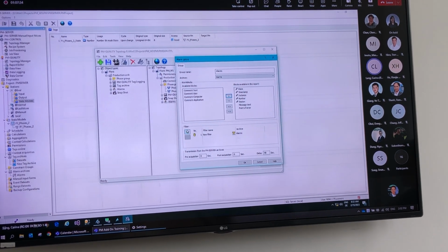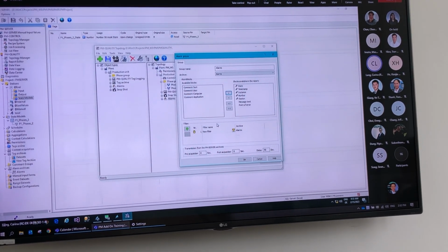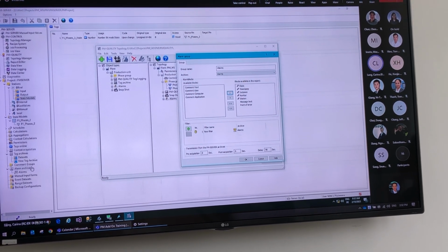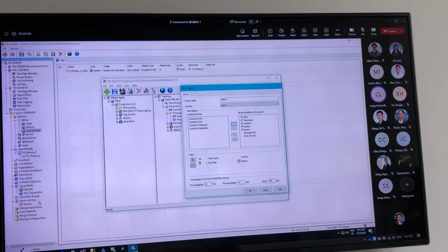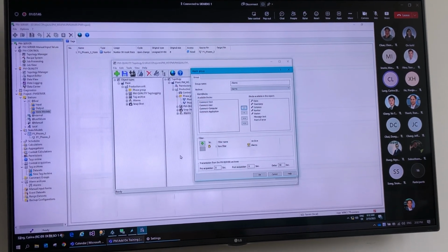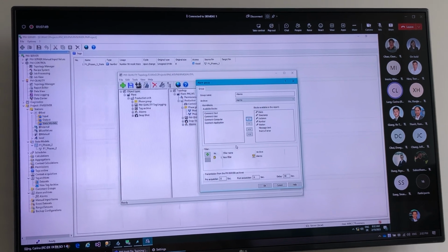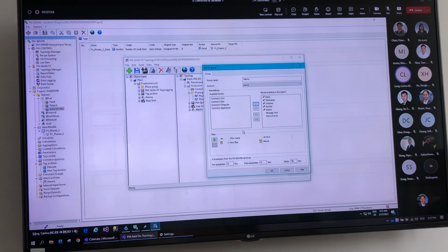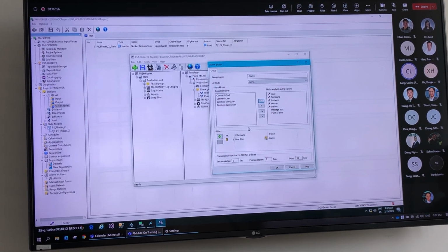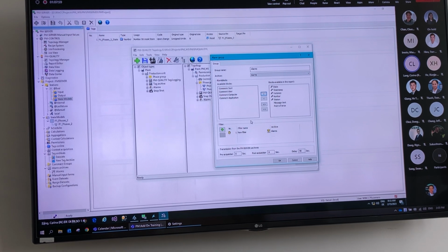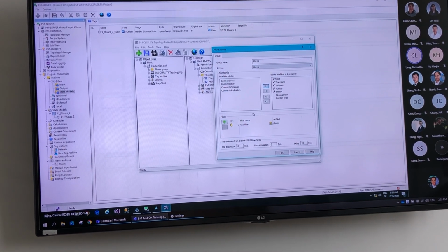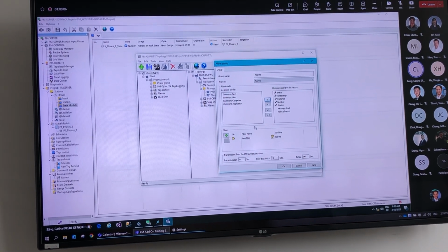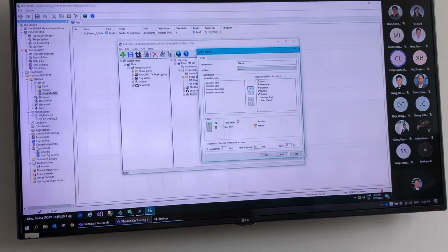And the filter here is working in a similar way. The difference is, if we do not store the alarms in the PM server, then of course they are not available for the PM quality, as they're not available in the PM server. If we filter inside of the PM quality, we still have the alarms available in the PM server, so we can have the alarm list and then go through all the alarms, for example. But inside of our report, we do not get all of these alarms, as we can set and filter here in this alarm group.